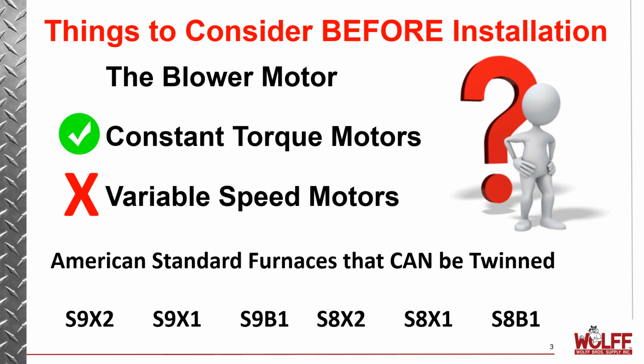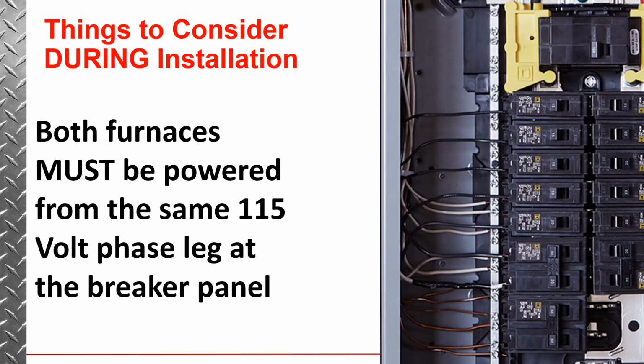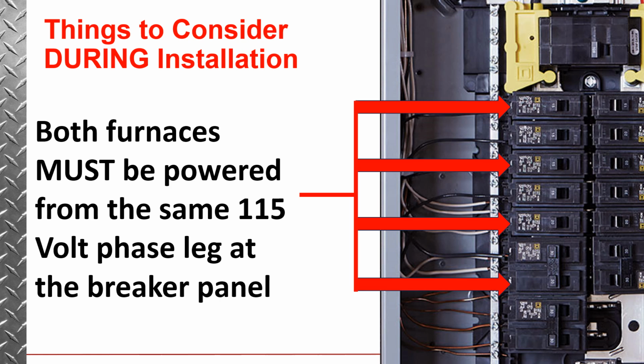That leaves you to American Standard furnaces that can be twinned, which would be the S9X2, the S9X1, the S9B1, the S8X2, the S8X1, and the S8B1. These all contain constant torque motors. Now during the installation, both furnaces must be powered from the same 115 volt phase leg at the breaker panel, which is basically every other breaker is the same leg.